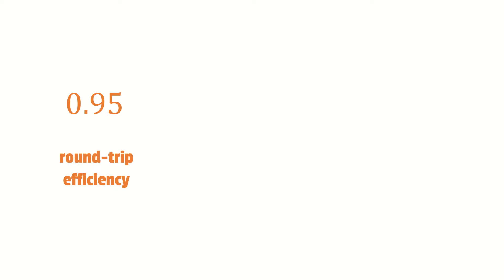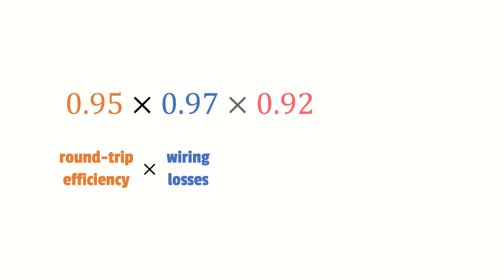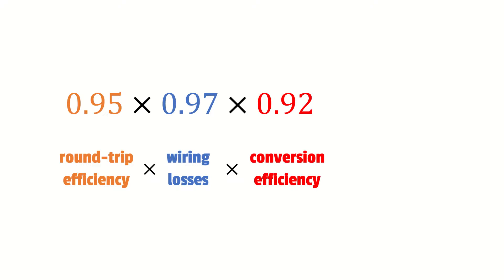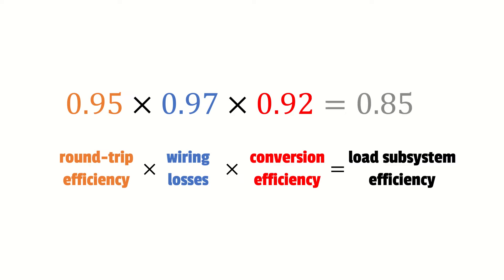Combining all system losses into a single factor: 0.95 for round trip efficiency, multiplied by 0.97 for wiring losses, multiplied by 0.92 for conversion efficiency, gives an overall load subsystem efficiency of 85% or 0.85.